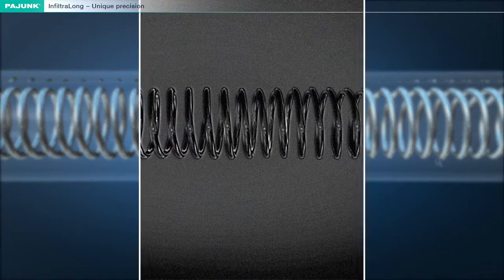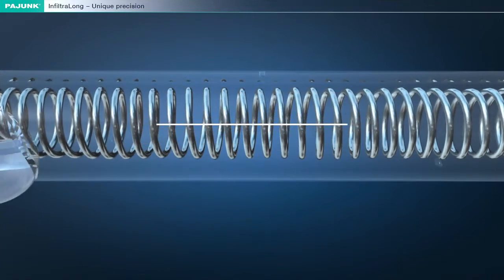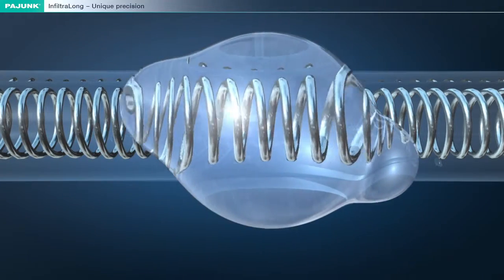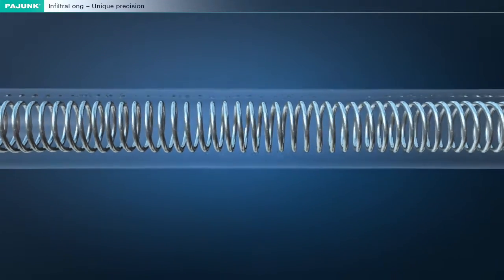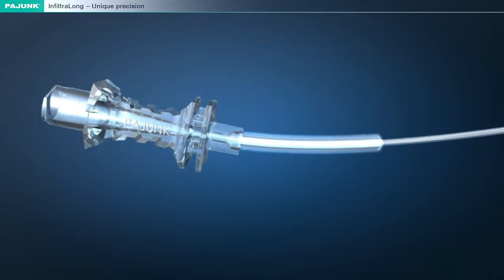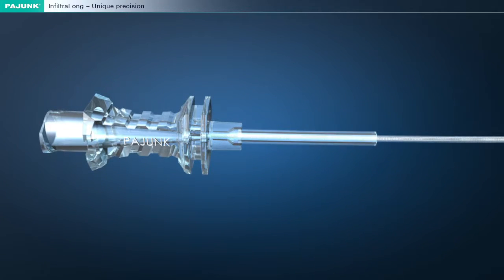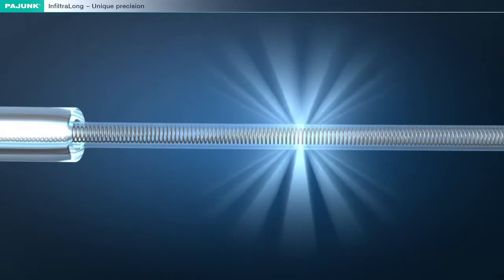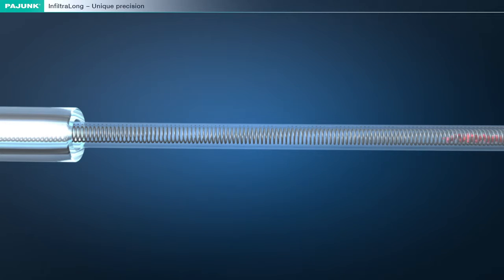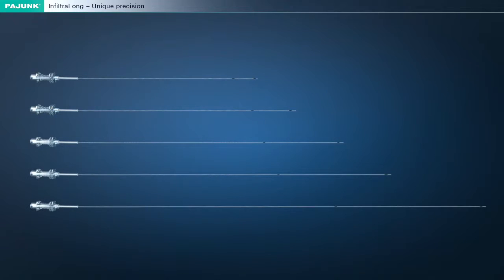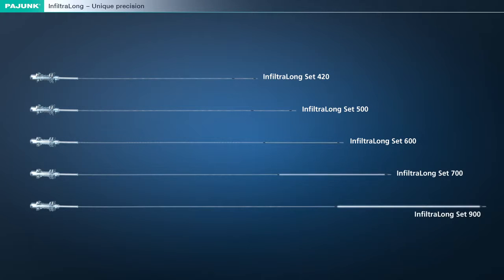The integrated stainless steel helical coil is visible under ultrasound, and it is also radiopaque. It guarantees a constant flow of the anesthetic, and it protects the catheter optimally against buckling and creasing. And the kink protection at the hub of the catheter will furthermore ensure operational safety outside the incision. The catheter itself consists of transparent polyamide. If the catheter is misplaced, then the inflow of blood can be detected instantly. This permits an immediate reaction. With a diameter of 19 G, the InfiltraLong catheter is available in 5 different catheter and perforation lengths, providing the size suitable for every incision.